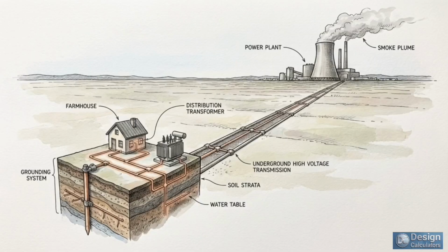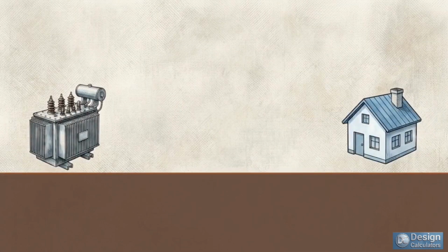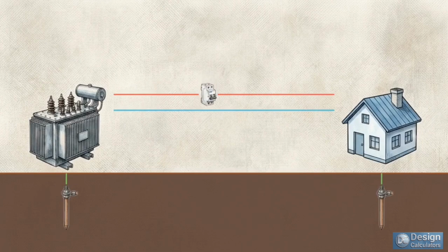In rural areas, overhead power lines are exposed to weather and falling tree branches. Relying on a continuous safety wire all the way back to a distant power plant is too risky. That environment requires the TT or terre-terre system. As shown here, the home uses its own independent grounding rod driven straight into the local dirt, completely physically separated from the power plant. The flaw in this design is the dirt itself. Natural soil has very high electrical resistance. A fault current struggles to push through the earth, arriving too weak to trigger a standard heavy-duty circuit breaker.